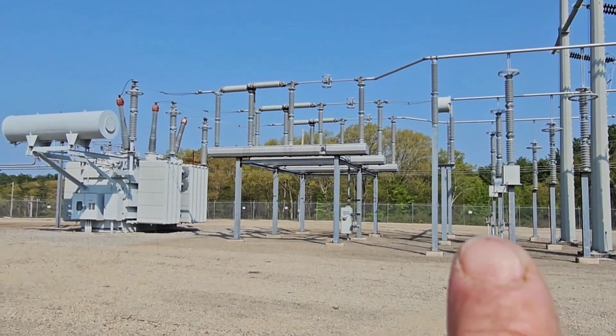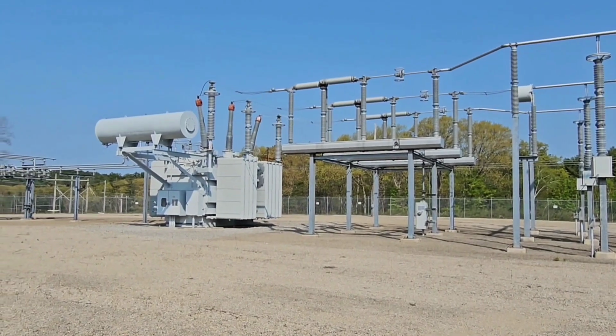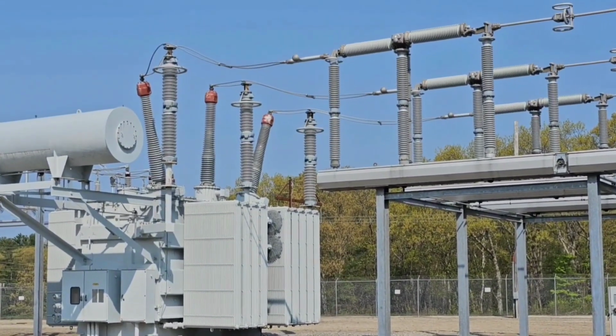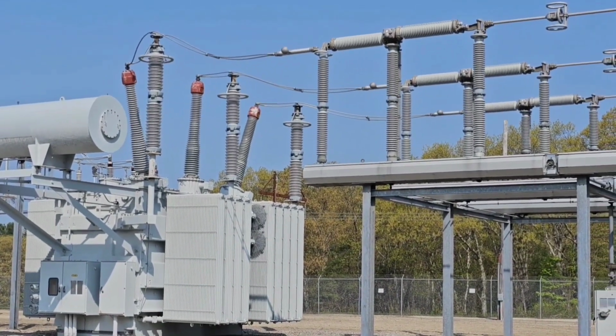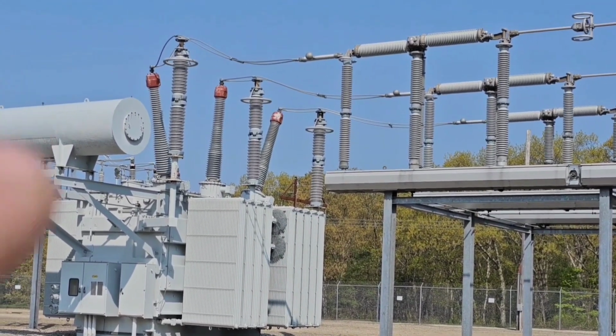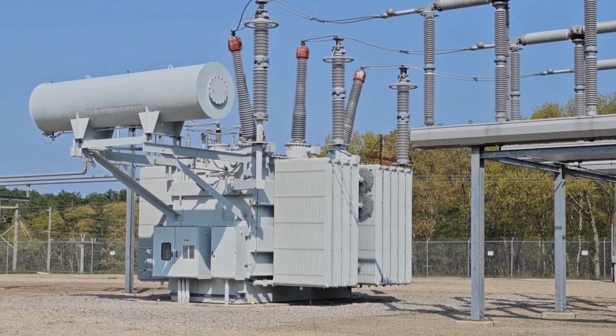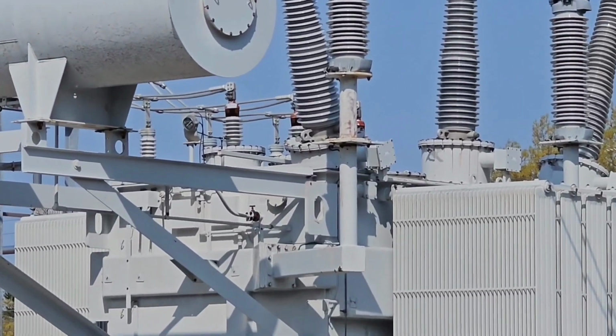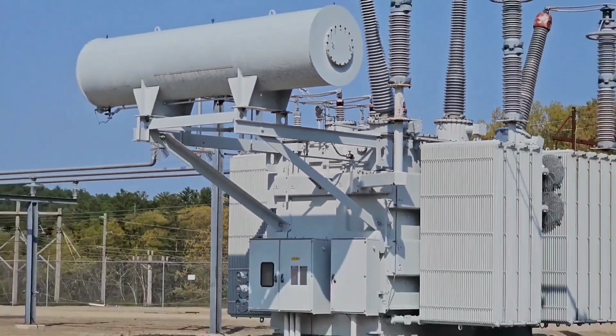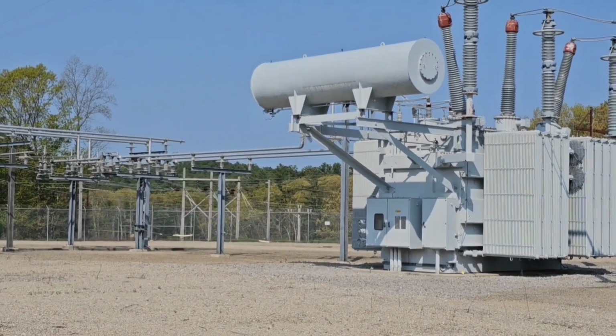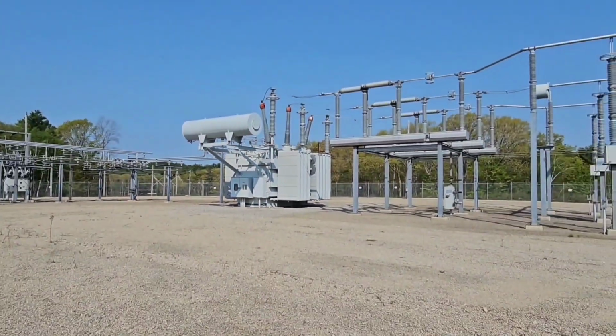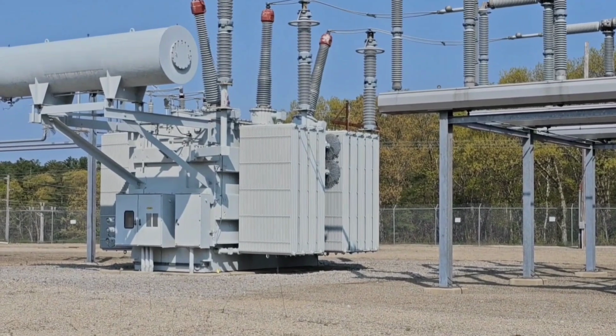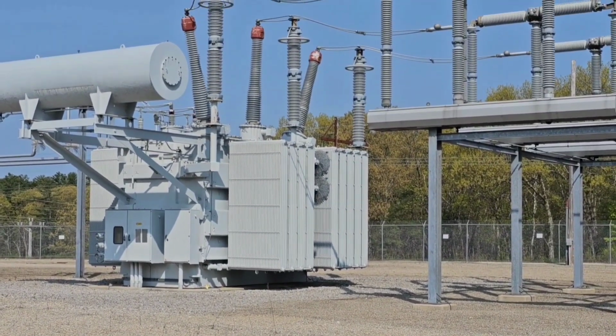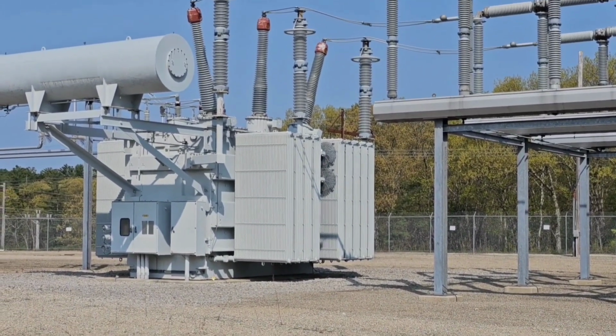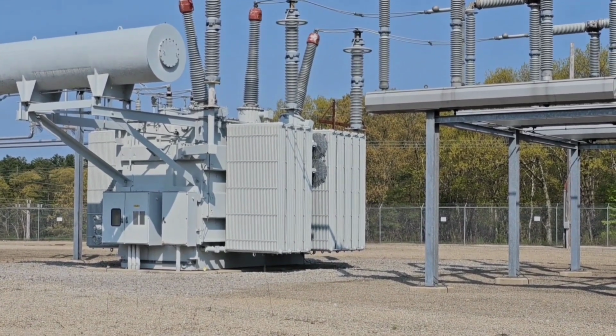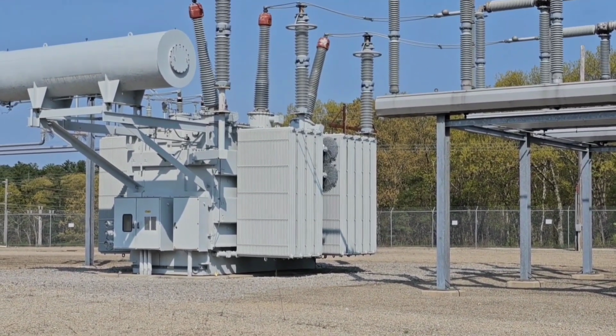The power comes in through this transformer, and you see these very large bushings on what's called the high side of the transformer. That's 345,000 volts. On the low side of the transformer, you see these smaller bushings. It comes out onto this bus at 34,500 volts. The way it does that is there are coils inside this transformer that transfer the power through induction and a ratio, which causes the voltage to drop and the current to go up.